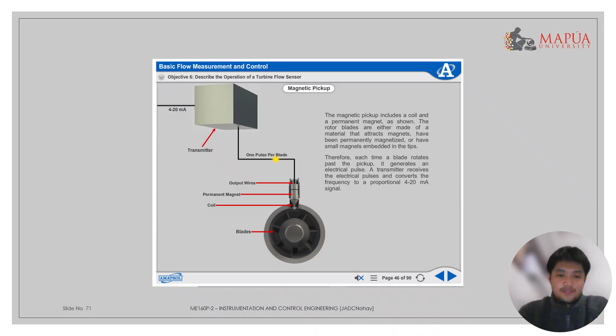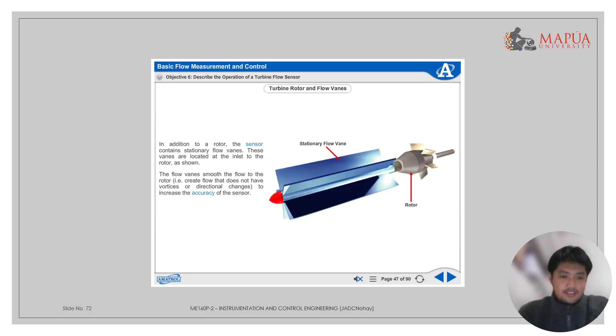A turbine rotor and flow vanes. In addition to a rotor, the sensor contains stationary flow vanes. These vanes are located at the inlet to the rotor as shown. The flow vanes smooth the flow to the rotor to increase the accuracy of the sensor.